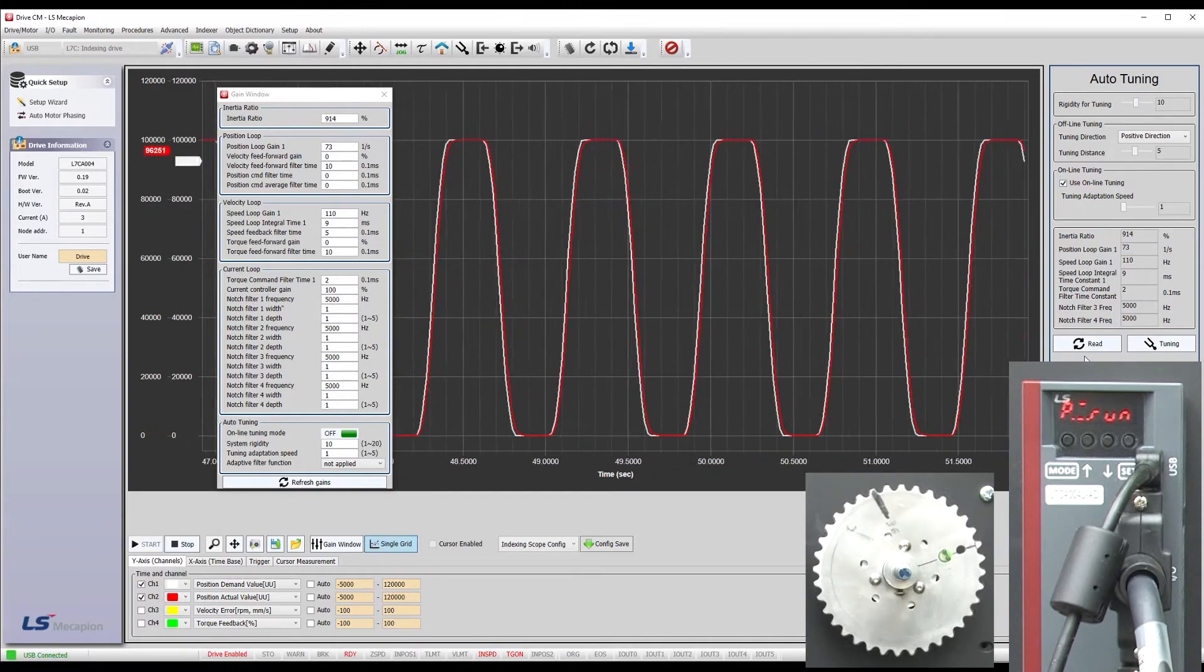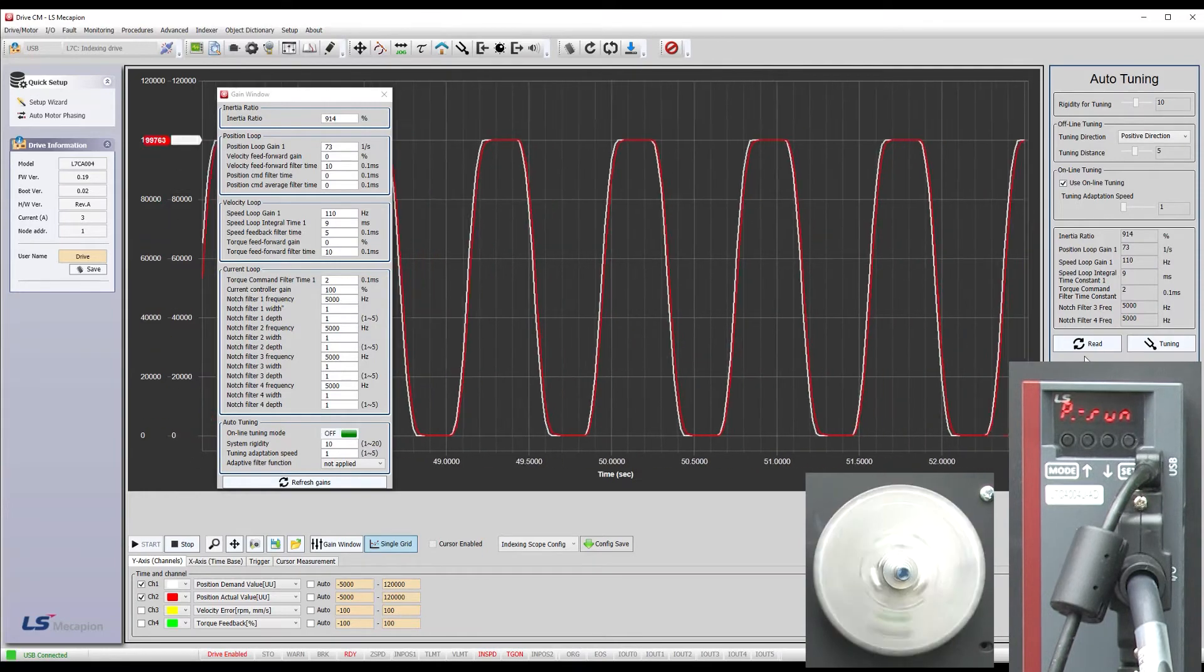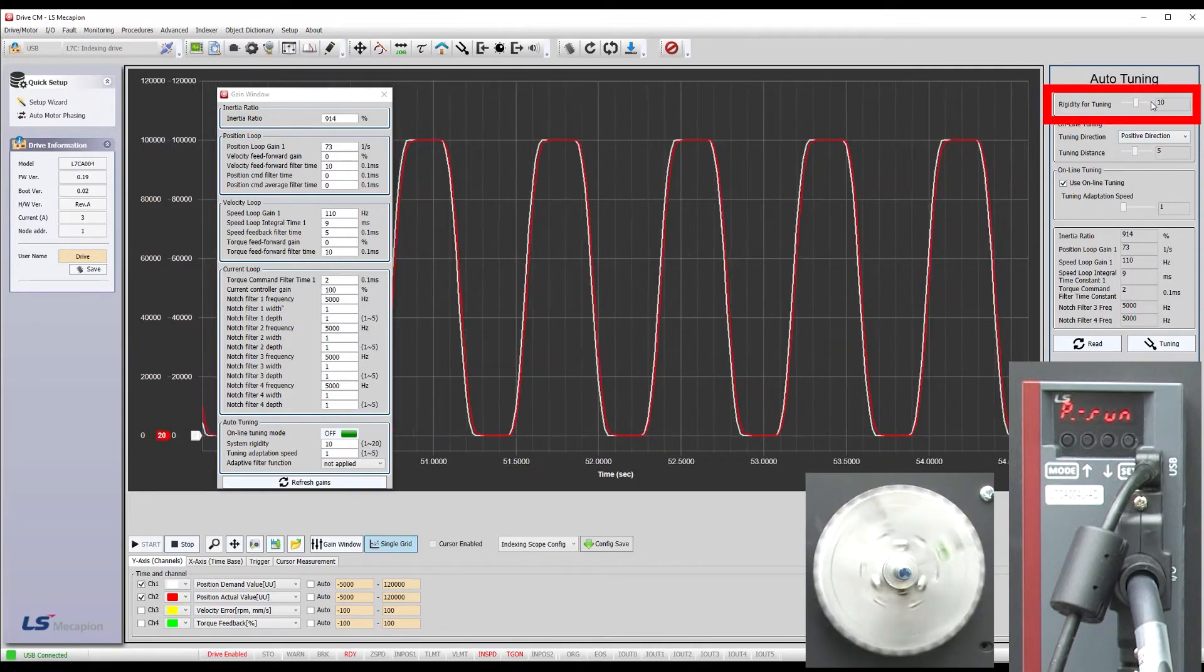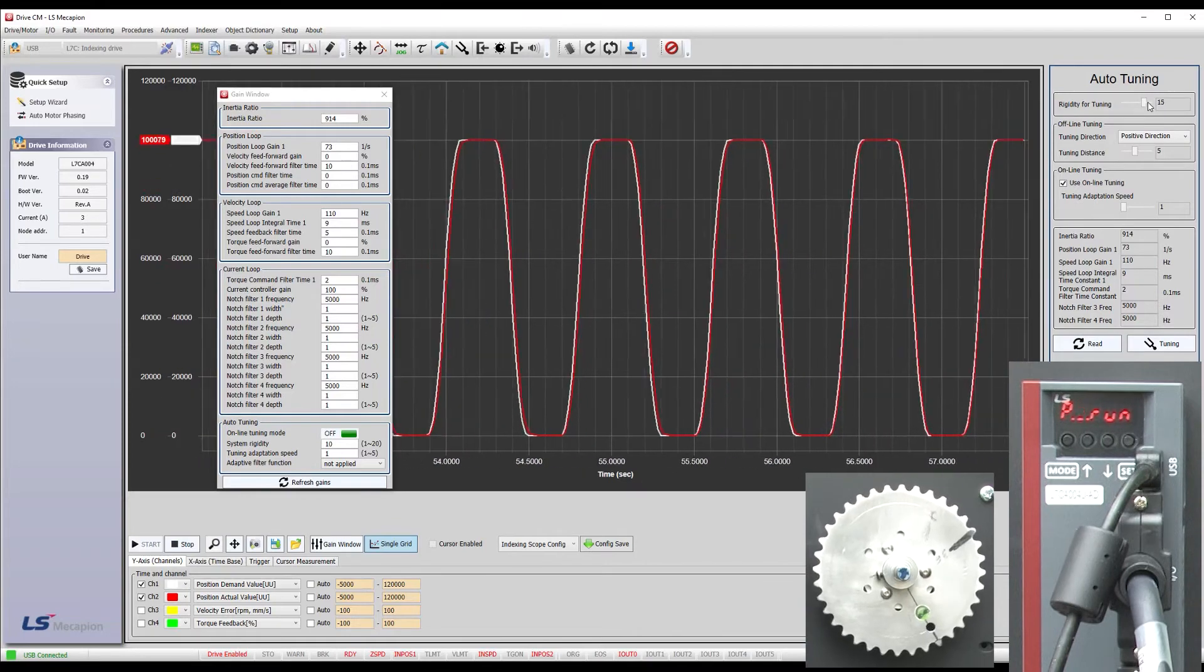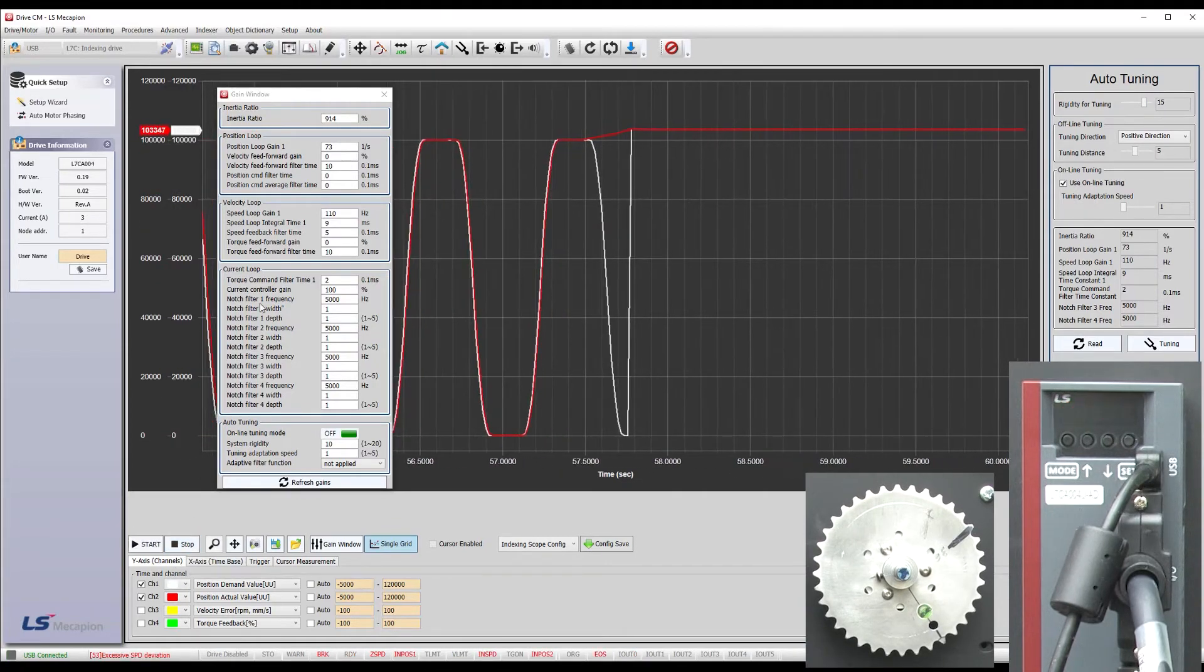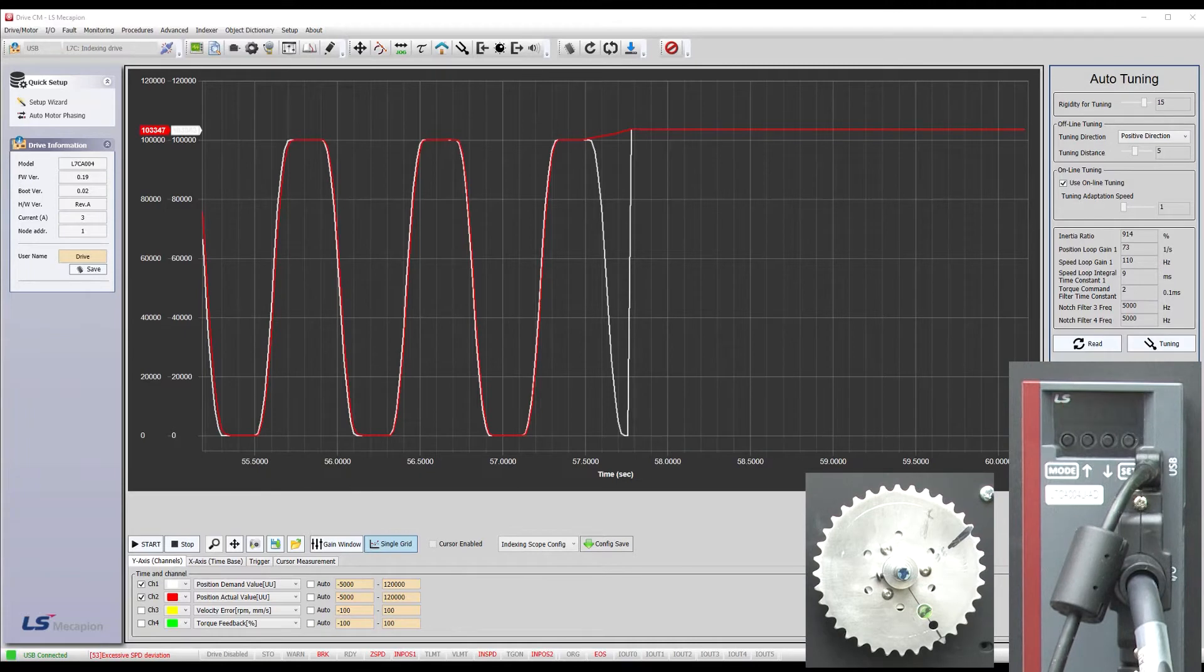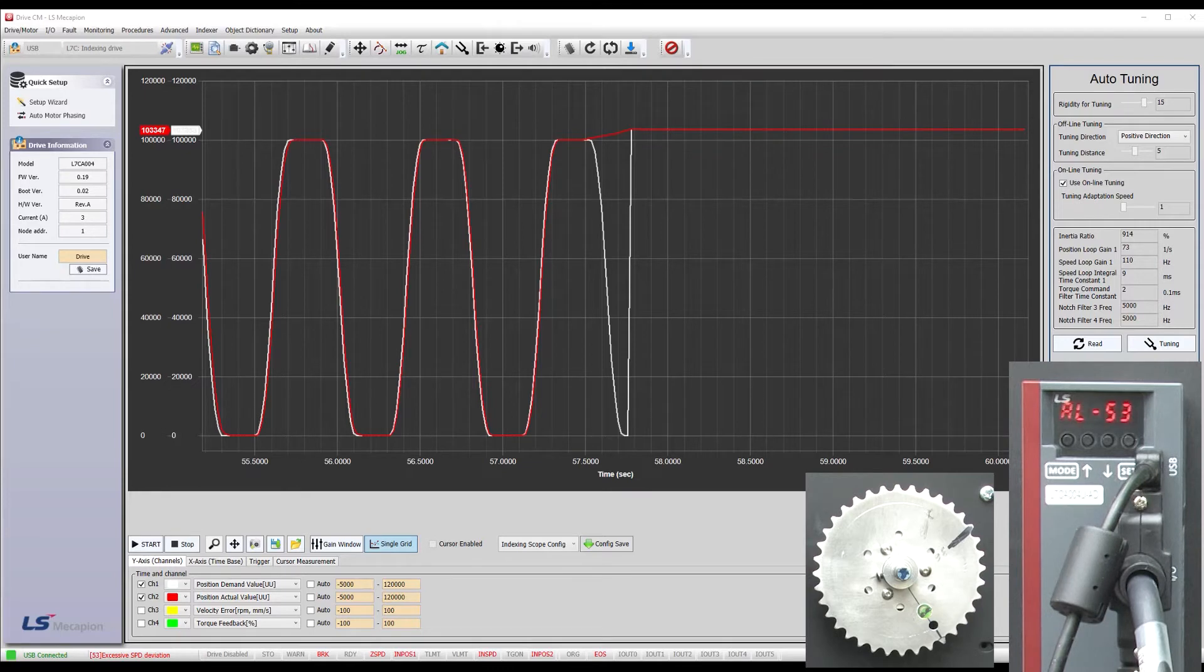This is important. Depending on your system, it is possible to get too rigid. I'll keep increasing the rigidity and oops. The drive couldn't maintain position as rigid as we requested so it gave up and issued an alarm. It says nope, can't do it. This alarm says the deviation between where we wanted to be and where we actually are is just too large and the drive can't pull it back in. Which is what we expect.